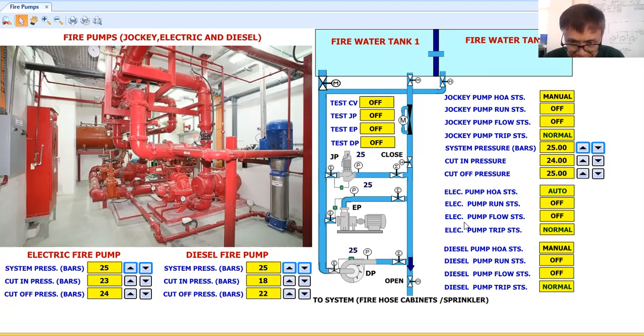So when we are testing this one, during testing and commissioning, the electric pump will be tested in no flow condition, meaning this valve will be closed. Then your electric pump will be allowed to run. So it will run without flow, or zero flow. Now I have here the flow meter. I have here one flow meter.